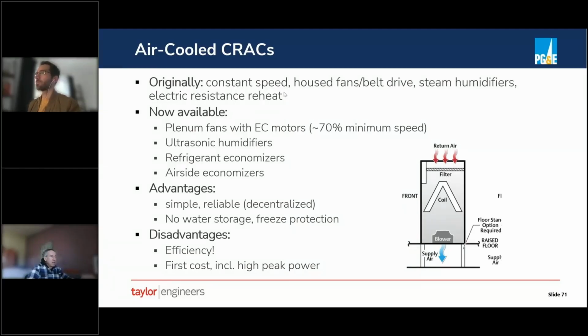One thing we found with data centers like that is that the humidity sensors that the crack units were using would drift out of calibration. And so it would be very common for one CRAC unit to be humidifying and the one right next to it to be dehumidifying with the electric resistance reheat. Very inefficient and basically constant speed fan.